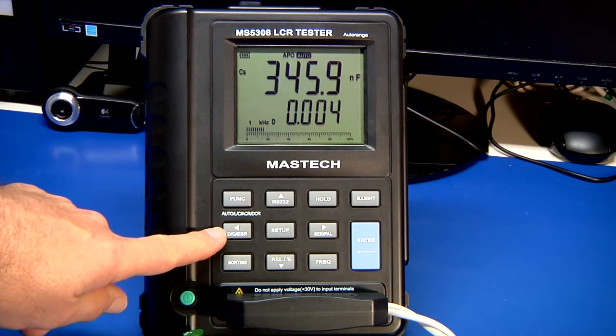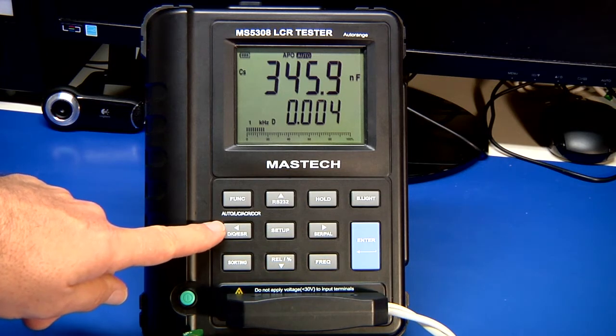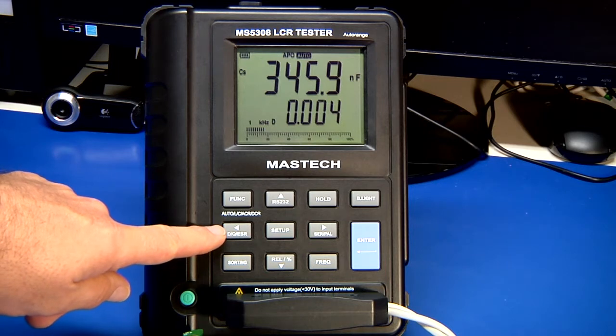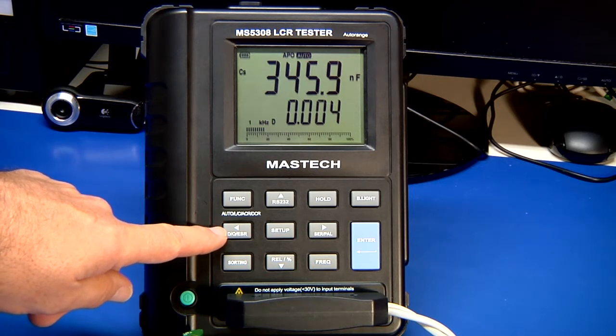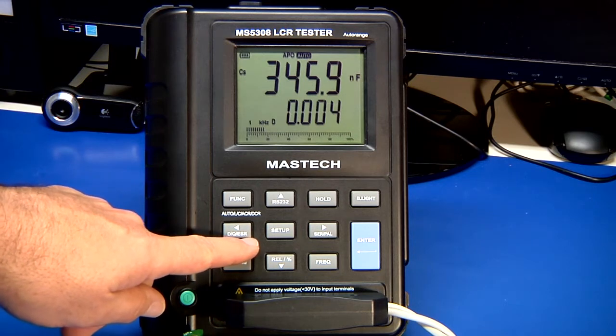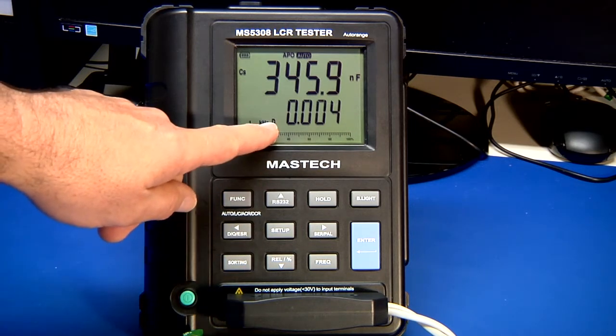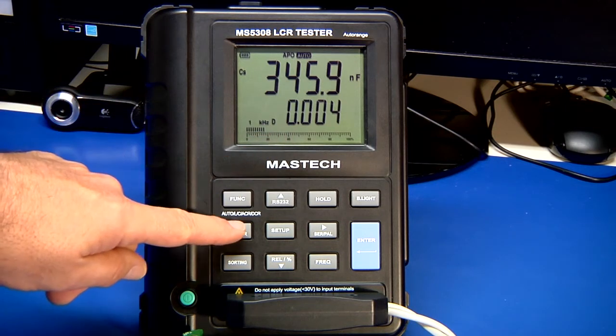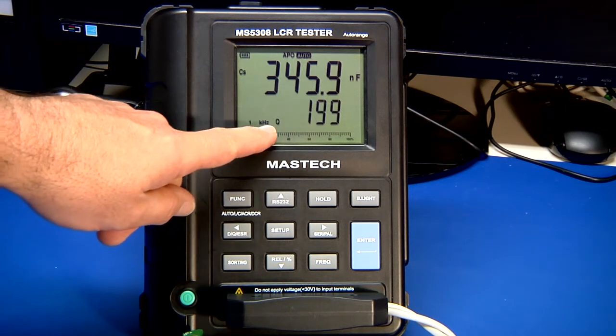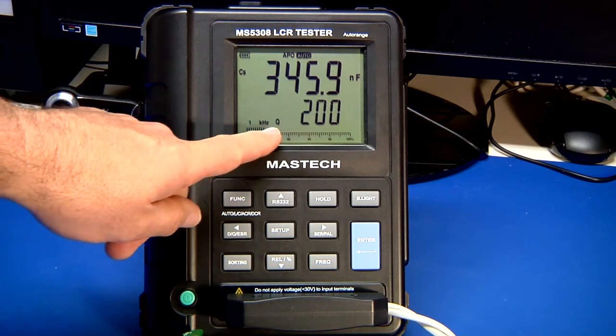This one is your secondary parameters, possibly. Here's where you have the dissipation factor, the Q, the ESR, equivalent series resistance. It doesn't show it, but there's actually a theta, which is the phase angle, and it is on there, and you cycle through it. So typically for capacitors, you do dissipation factor; for inductors, you would do the Q. They are reciprocal properties.